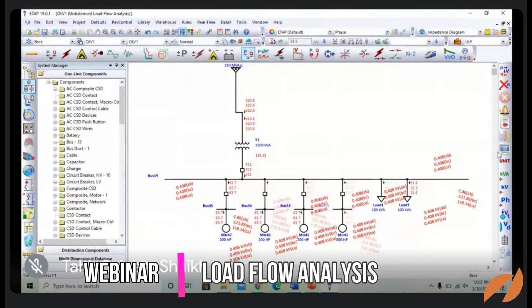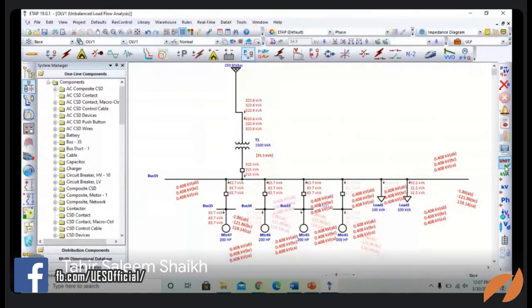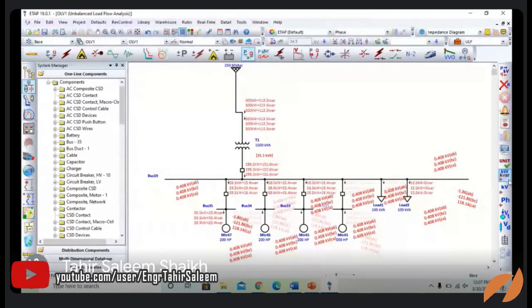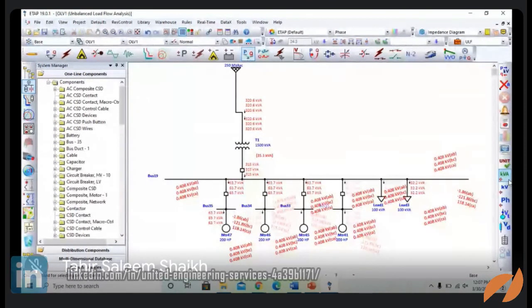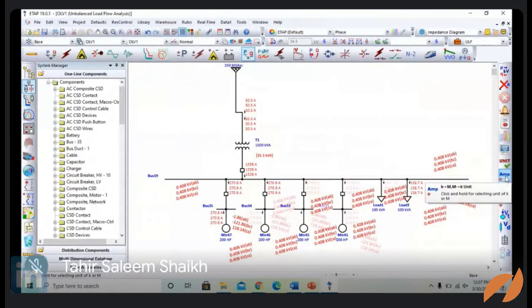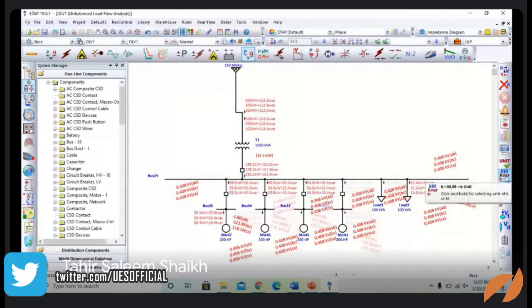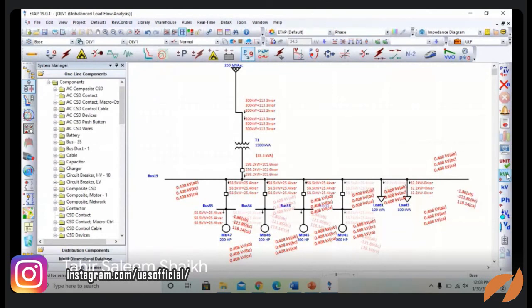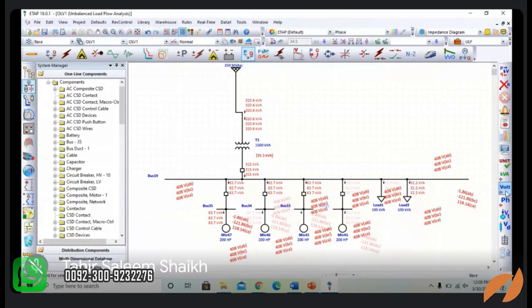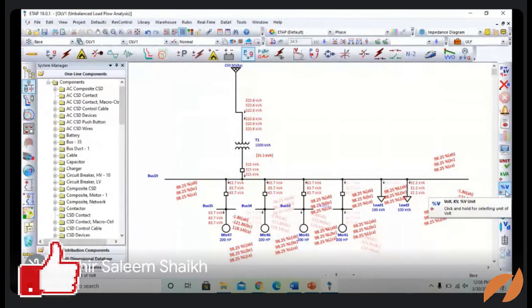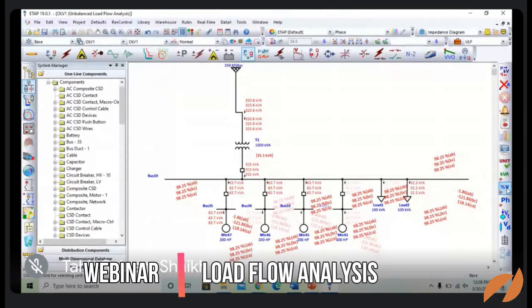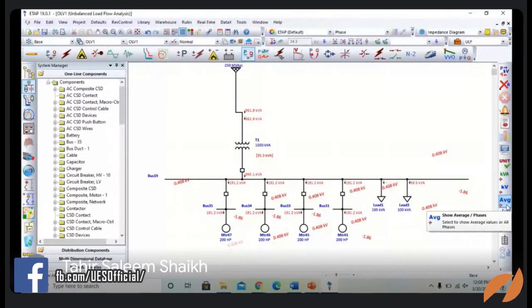And in the display option, you can change the unit if you want the unit to be shown over here, and you can also generate a report for that. And if you want to just change the unit, like here, you can see kVA. Okay, this is ampere. Okay, this is the kilowatt plus kVAR loading. And if you want to change the voltage angle, voltage percentage, like if you want the voltage in percentage, you will see here 98.25 the voltage. So these are the options. Yeah, within limit.